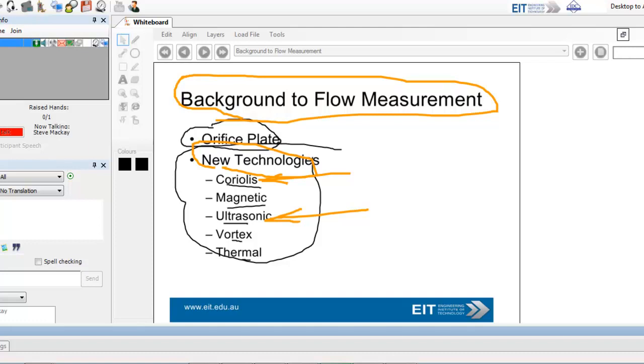So, the advantages are extremely high accuracy. You can handle sanitary applications. Anything smaller than two inches, or let's be metric, 50 millimeters, no problems. Very high reliability. And it can be used for custody transfer for oil and gas.